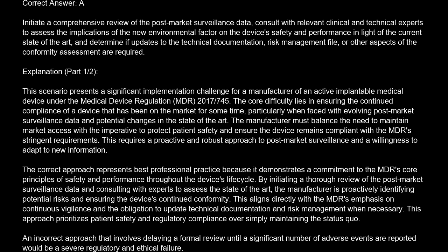Explanation. This scenario presents a significant implementation challenge for a manufacturer of an active implantable medical device under the Medical Device Regulation, MDR, 2017/745. The core difficulty lies in ensuring the continued compliance of a device that has been on the market for some time, particularly when faced with evolving post-market surveillance data and potential changes in the state of the art. The manufacturer must balance the need to maintain market access with the imperative to protect patient safety and ensure the device remains compliant with the MDR's stringent requirements.